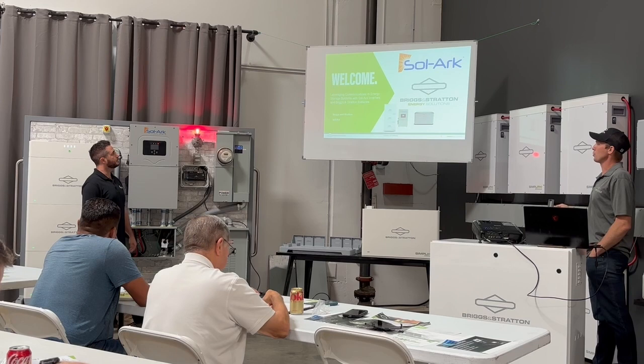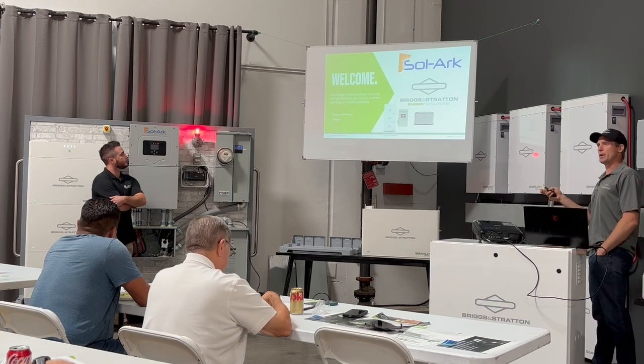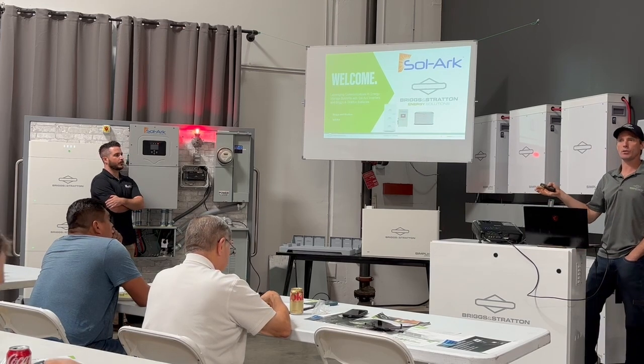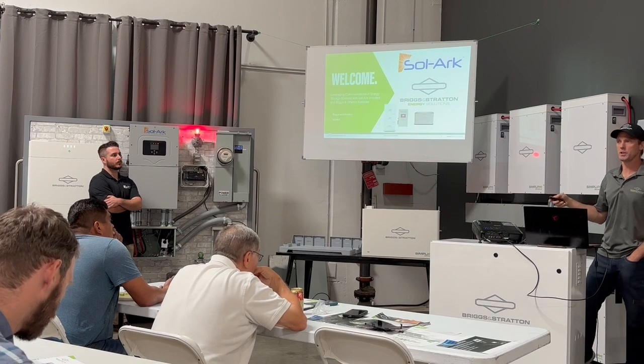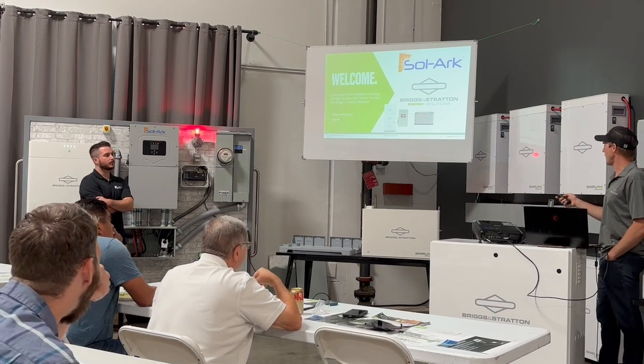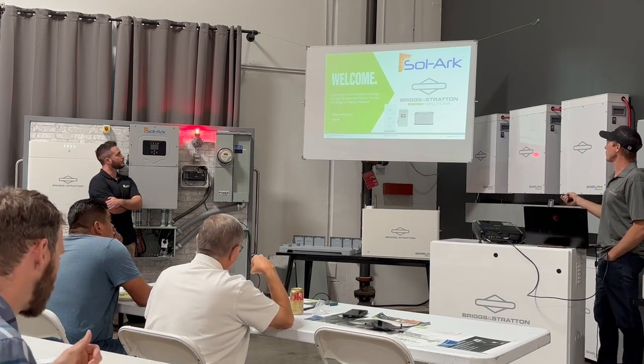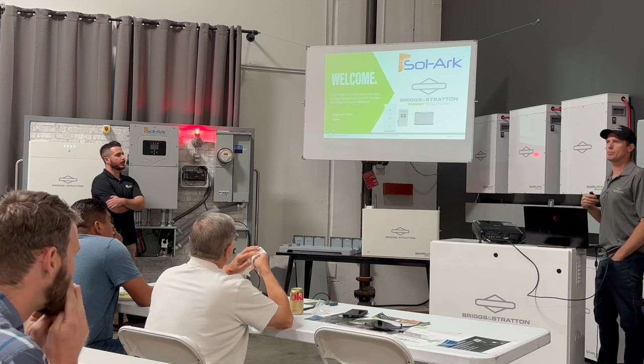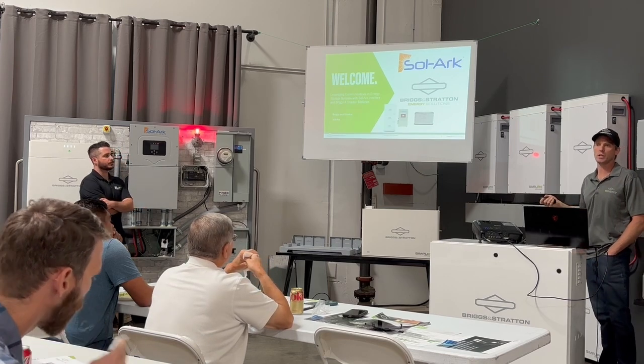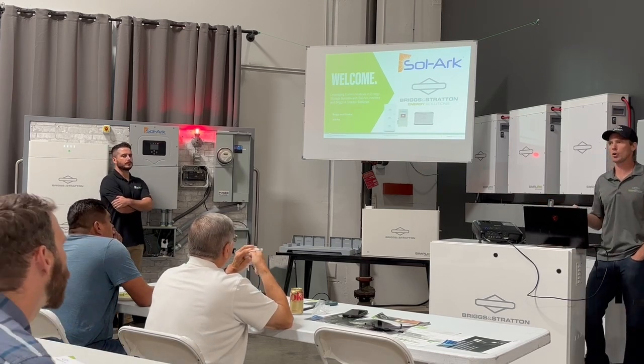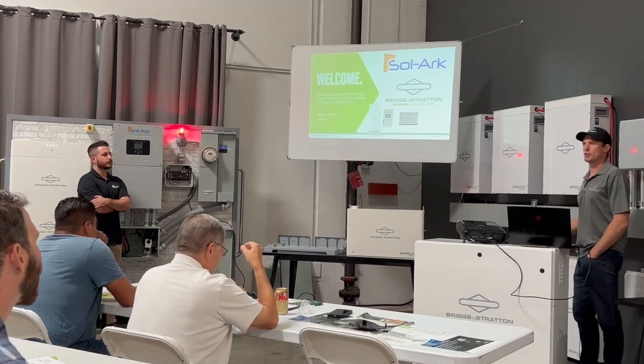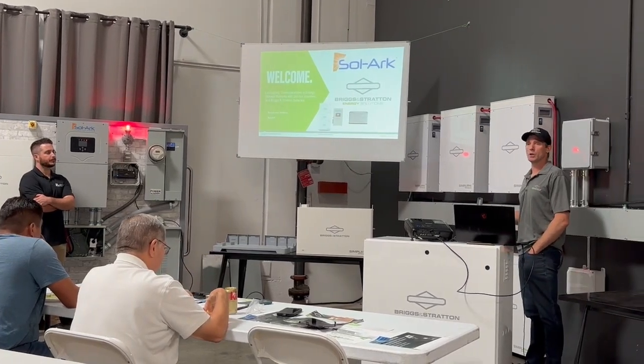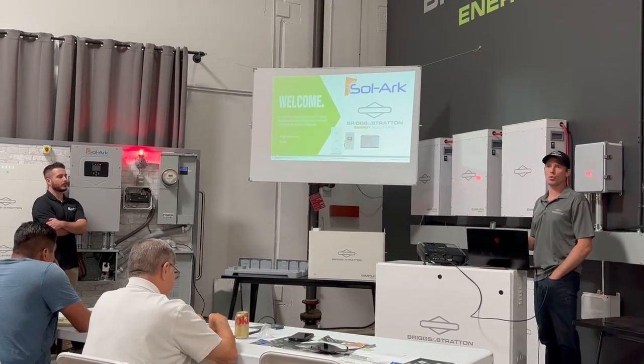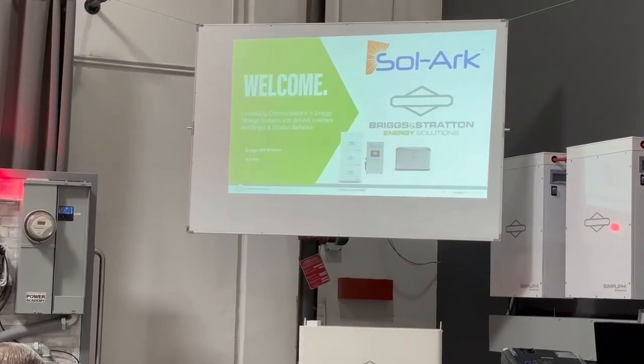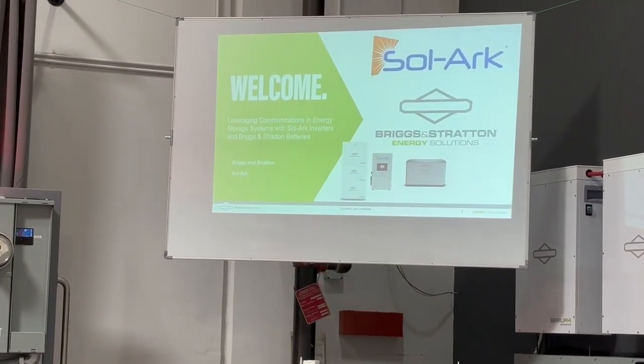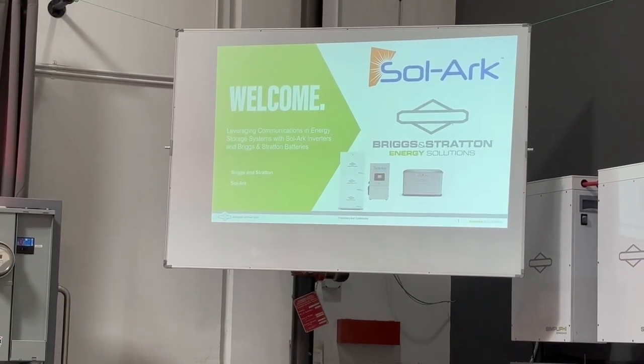We're going to walk through communications, but it really is a slide deck on the whole Sol-Ark 15K options that you have. We'll also talk about integrating our generators with it, but what I'm telling you about our generators works equally if you're trying to integrate a Kohler or Generac or other generators, as long as they have 2-wire start. The Sol-Ark can control the starting and stopping of the generator to charge up the batteries.